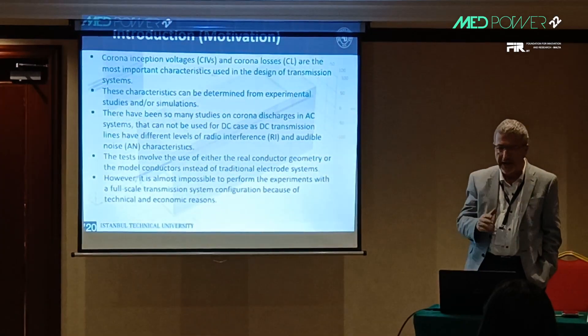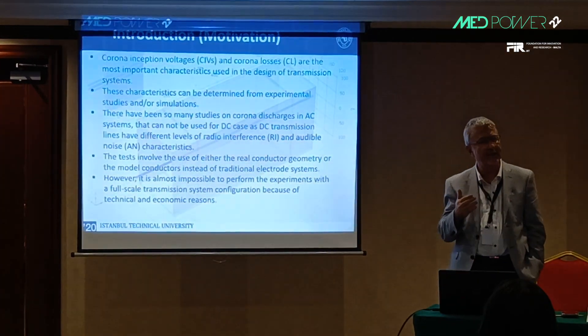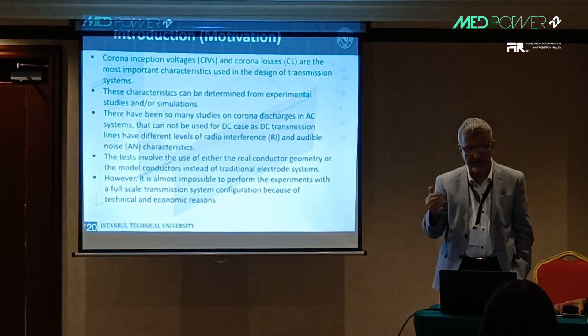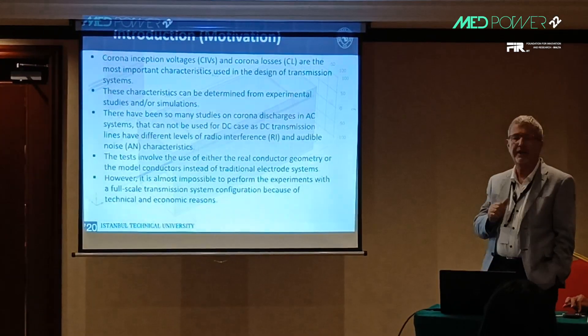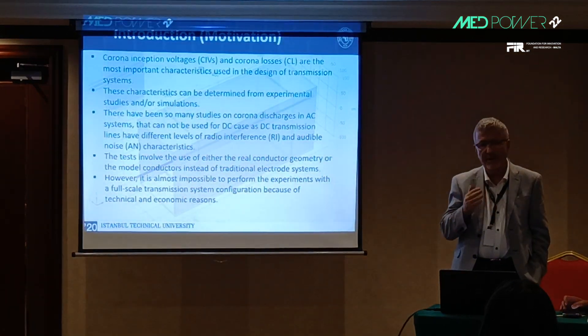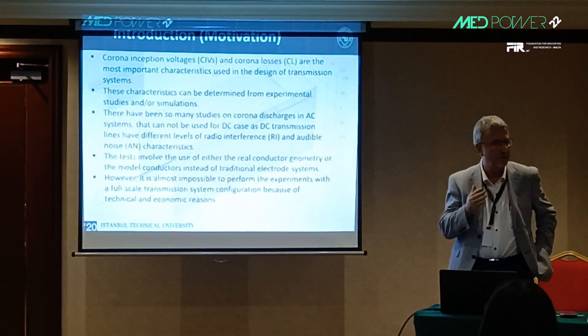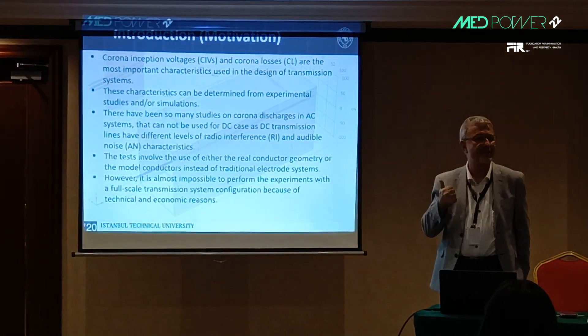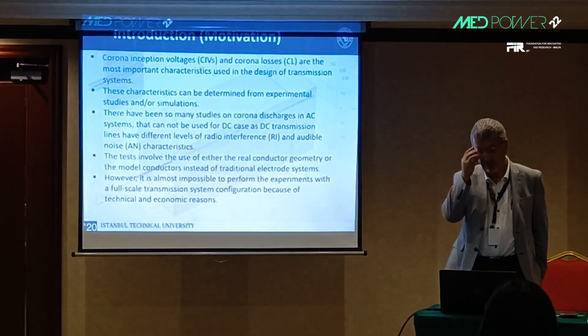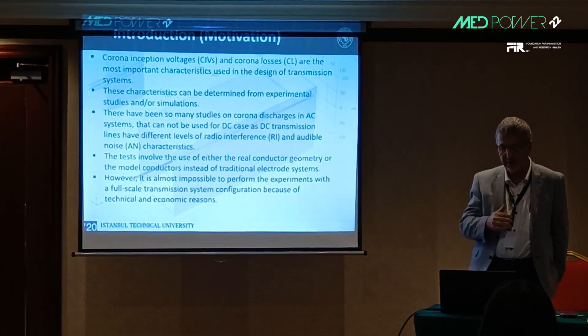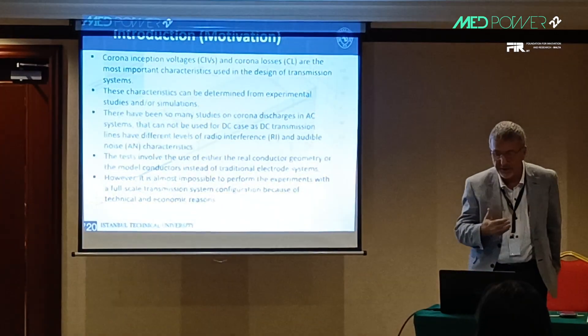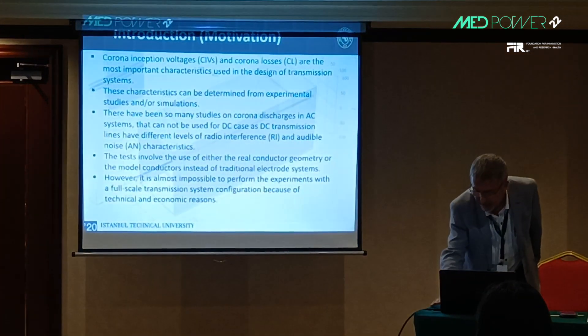The new HVDC line is about 600 kV, and the length will be 1,000 km. We needed some tests and some design criteria. We dealt with the corona side of that transmission line and tried to give some idea about the corona characteristics for the prospective line and line configurations. Although there are several similar studies on the AC side, we could not use them because of some difficulties, so we needed a new experimental study to be carried out in a corona cage.